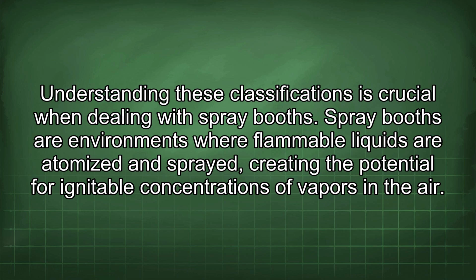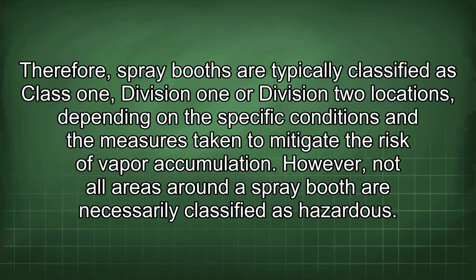Spray booths are environments where flammable liquids are atomized and sprayed, creating the potential for ignitable concentrations of vapors in the air. Therefore, spray booths are typically classified as Class 1, Division 1 or Division 2 locations, depending on the specific conditions and the measures taken to mitigate the risk of vapor accumulation. However, not all areas around a spray booth are necessarily classified as hazardous.